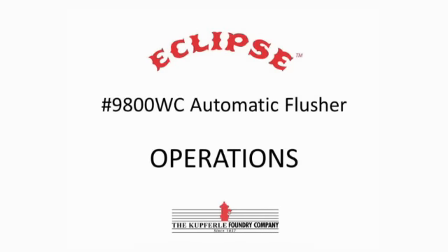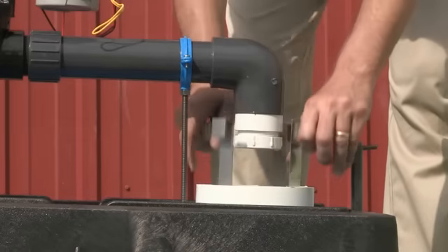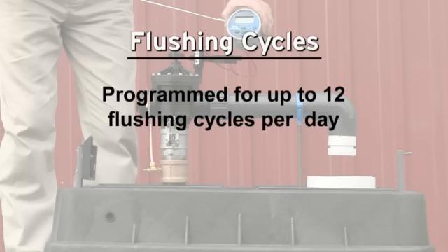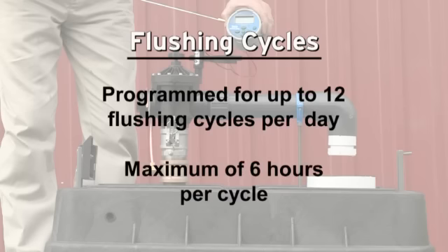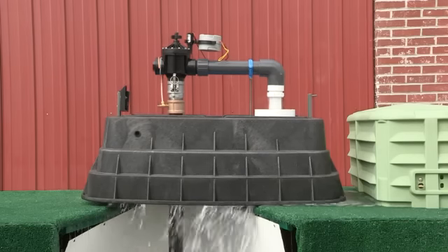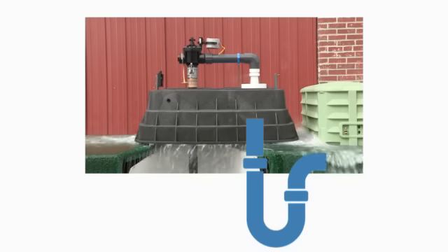The Eclipse 9800WC has an optional debris basket that fits inside the 6-inch outlet. The handheld controller can be programmed for up to 12 flushing cycles per day with a maximum of 6 hours per cycle. Water flushes into a 6-inch discharge pipe and is directed to a sanitary or storm sewer, a culvert, or drainage ditch, as seen by this graphic illustration.